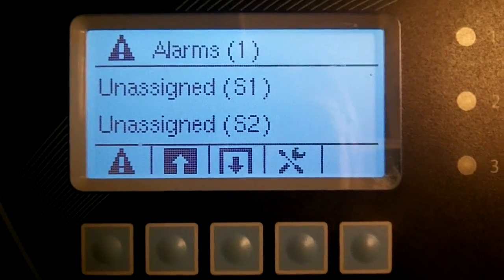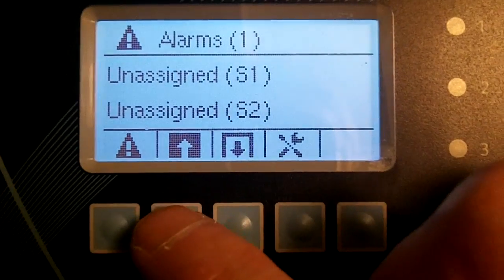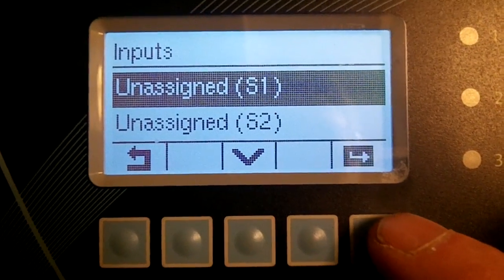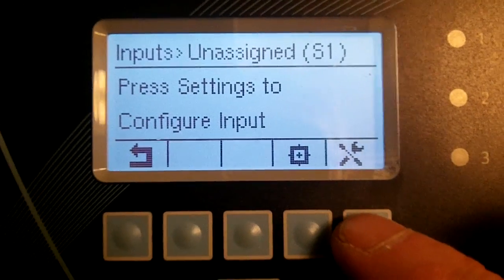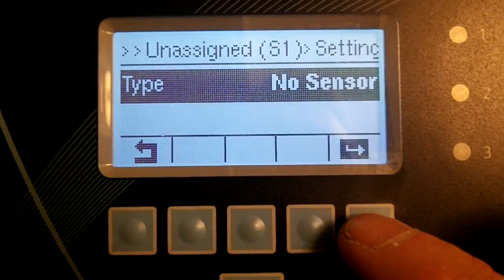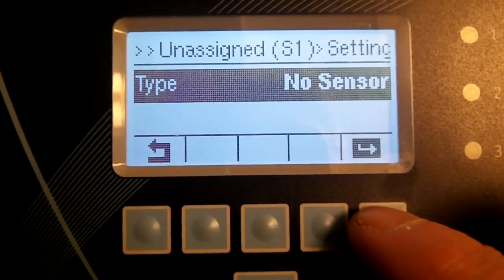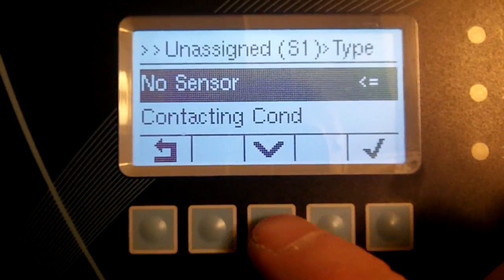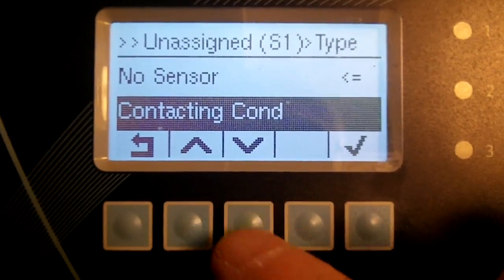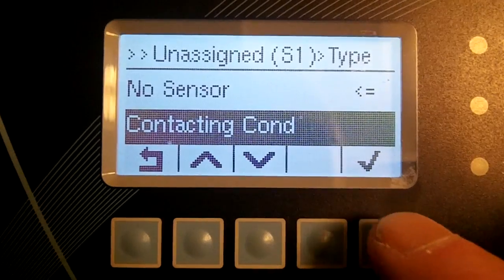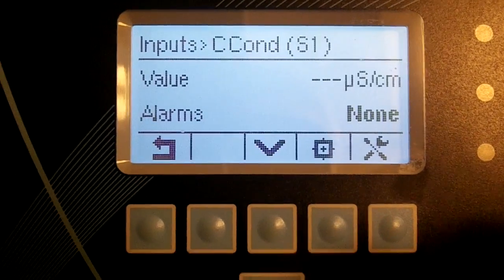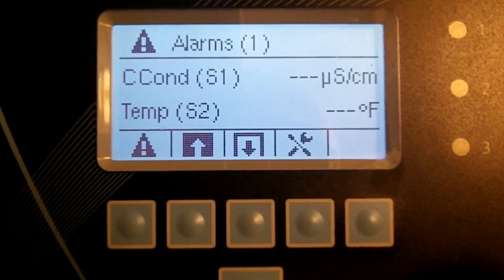Step 1: Select and configure sensor type for contacting conductivity. Navigate to Inputs, press Enter, then Configure. Press Enter, then use the down key until you reach Contacting Conductivity. Check it off and return to the home menu.